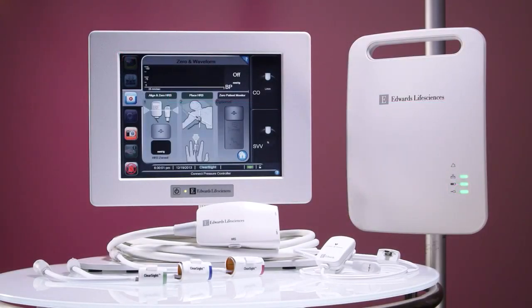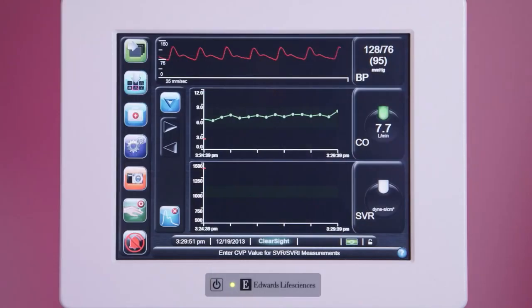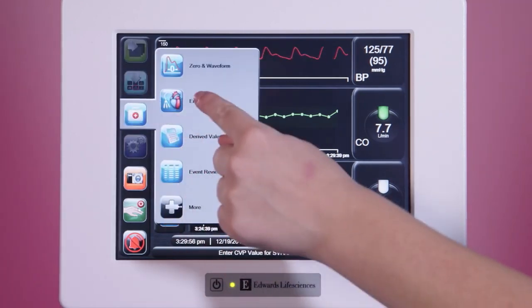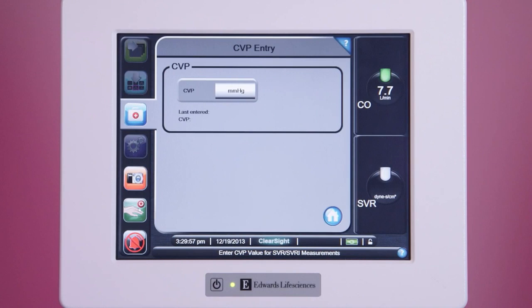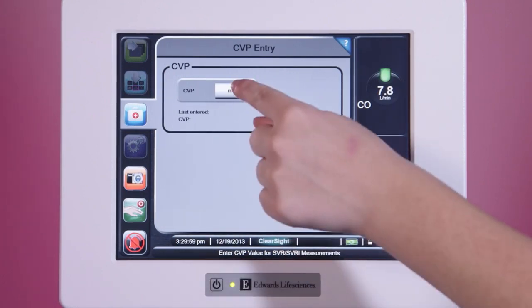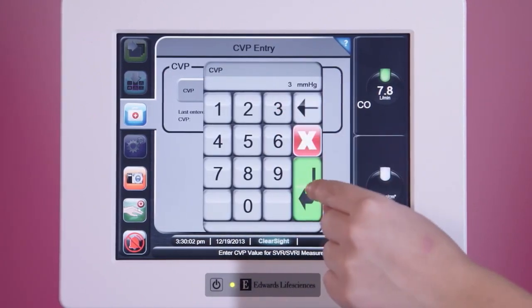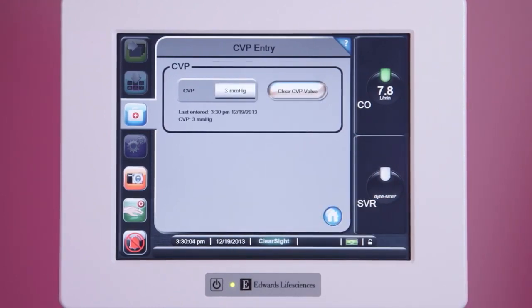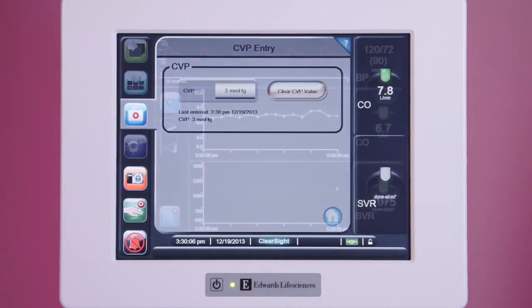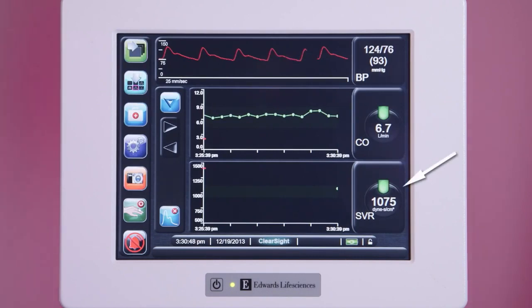The ClearSight system can provide a systemic vascular resistance if a CVP value is provided. To enter a CVP value, tap the Clinical Actions icon on the navigation bar and select Enter CVP. Tap on the gray rectangle and enter a CVP value in millimeters of mercury. Tap the Home button to confirm. The system will automatically start providing systemic vascular resistance. Note that if a CVP value is entered, it must be updated by the clinician as its value changes.